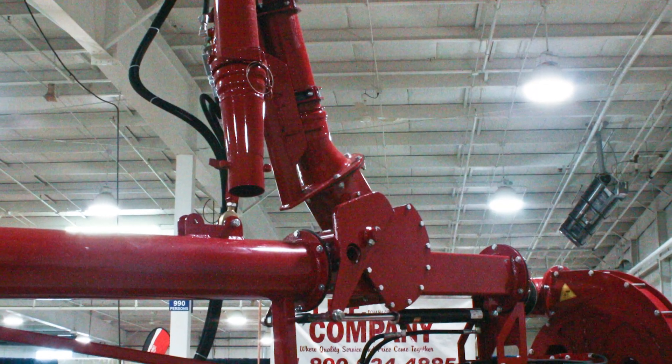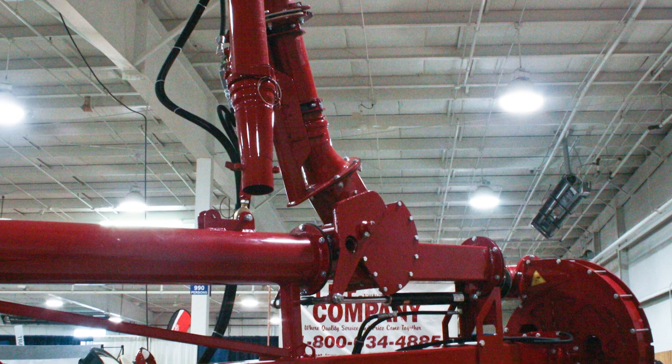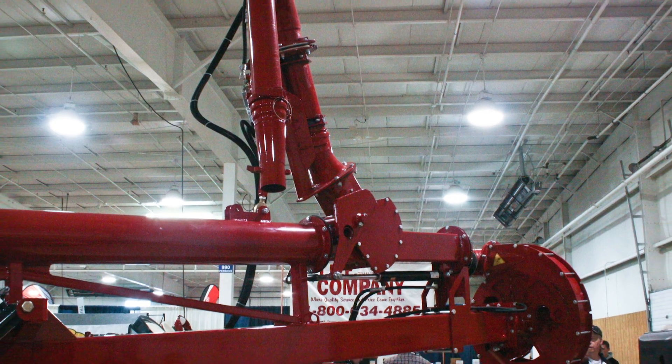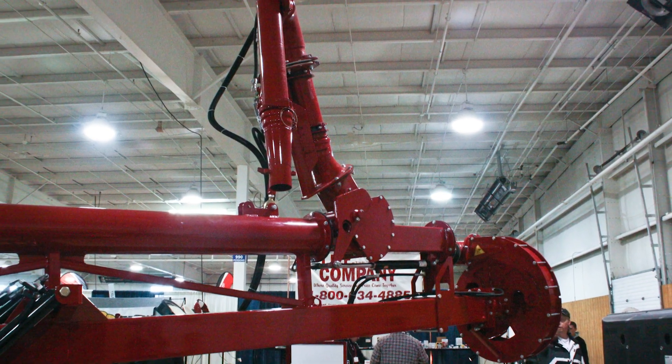There are really two other designs on the market: a vertical design with a standard housing used just for pumping, and a gearbox design with a propeller and an impeller for agitation of thick and heavy crusts. This pump functions as both and gives you the advantages of both — without a gearbox, which is one of the main issues in lagoon pumps due to replacement time and wear on gearboxes.